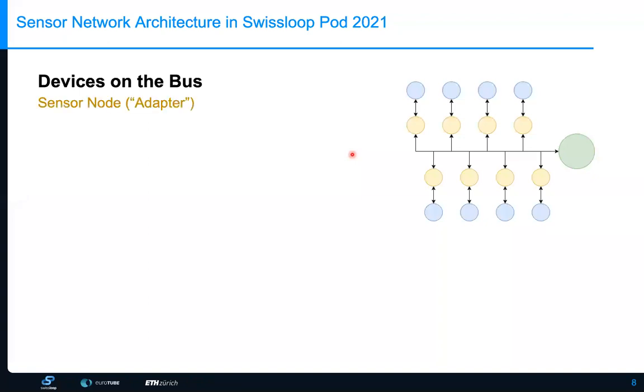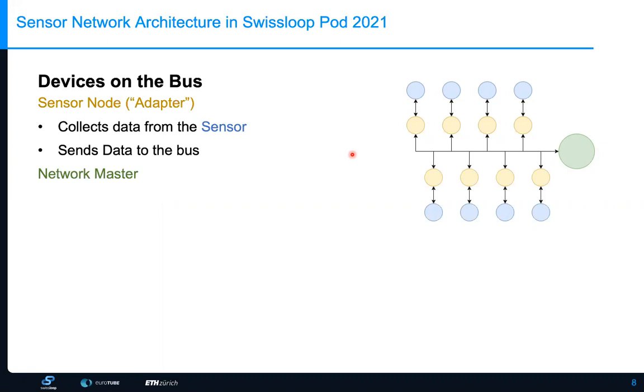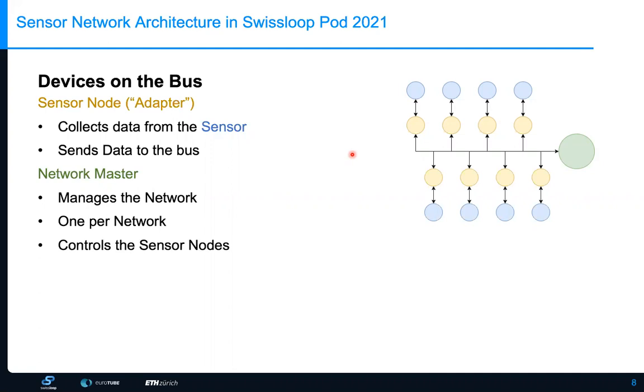There are different devices on the bus. The first is the adapter, which translates sensor data to a common communication protocol for the bus, collects data from the sensor, stores it, and then sends it on the bus. The second device is the network master, which controls everything on the bus — it handles who can send data, configures everything, and there is one master per network. The network master is also responsible for controlling and configuring the sensor nodes.